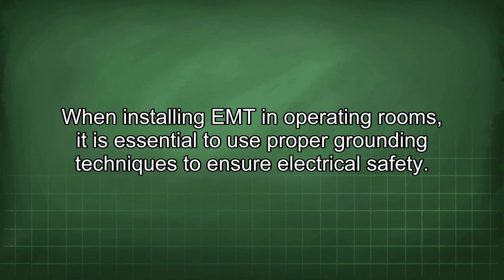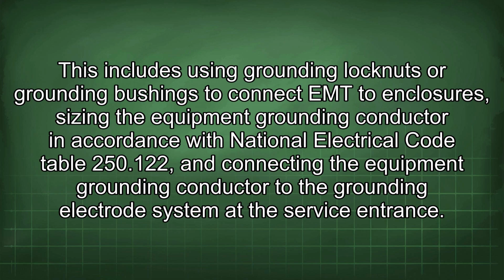When installing EMT in operating rooms, it is essential to use proper grounding techniques to ensure electrical safety. This includes using grounding locknuts or grounding bushings to connect EMT to enclosures, sizing the equipment grounding conductor in accordance with National Electrical Code Table 250.122, and connecting the equipment grounding conductor to the grounding electrode system at the service entrance.